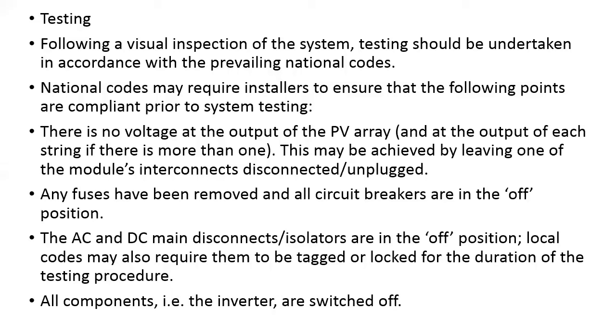This may be achieved by leaving one of the module interconnectors unplugged. And of course the next thing is to check that any fuses have been removed and all circuit breakers are in the off position. Then we have to check that the AC and DC main disconnectors or isolators are in the off position. Once they are in the off position, local codes may also require them to be tagged or locked for the duration of the testing procedure.